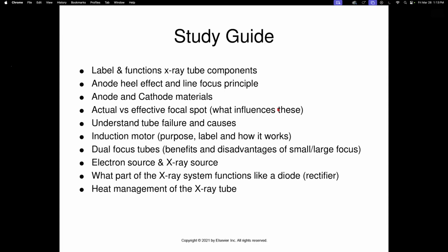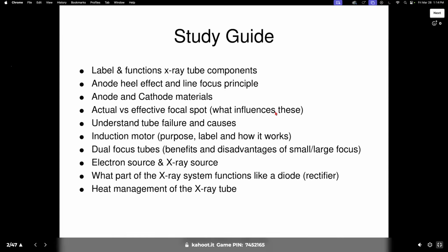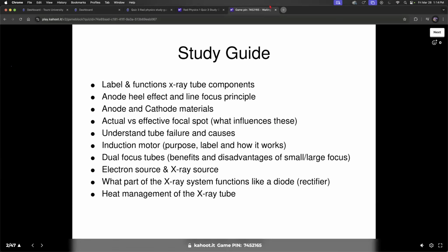So then bits of the anode peel off and they're off to the side. And then electrons, instead of going in a straight line, arc towards where they shouldn't go. Is that due to pitting? Pitting of the anode, yeah, so then it ends up in other places. That's exactly right.